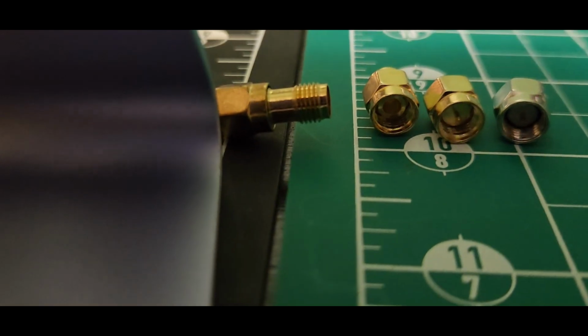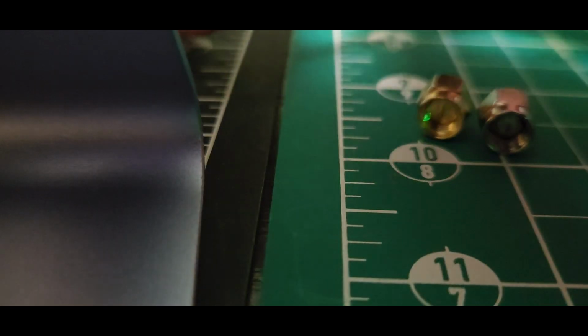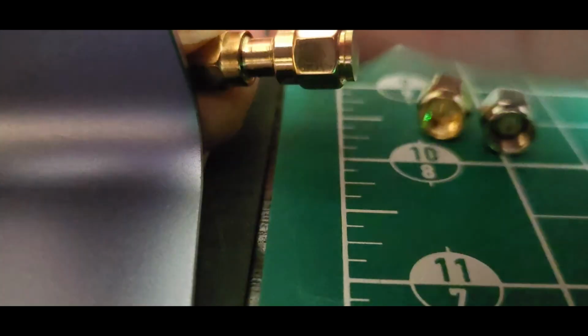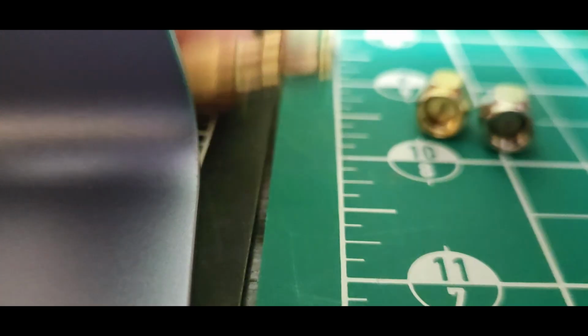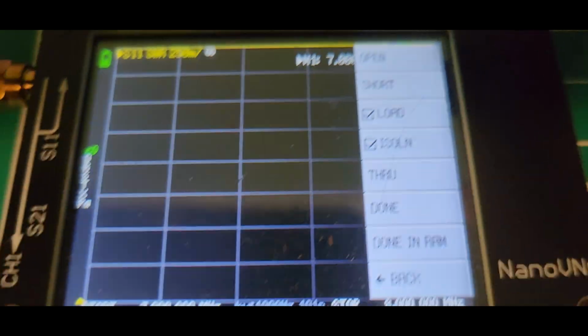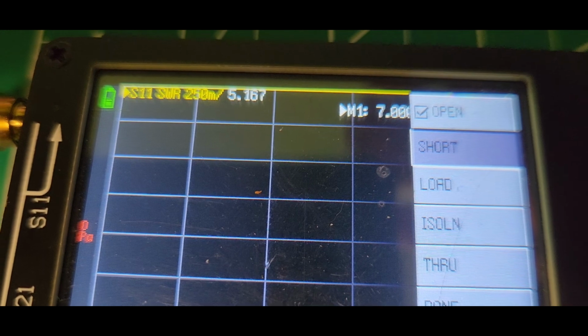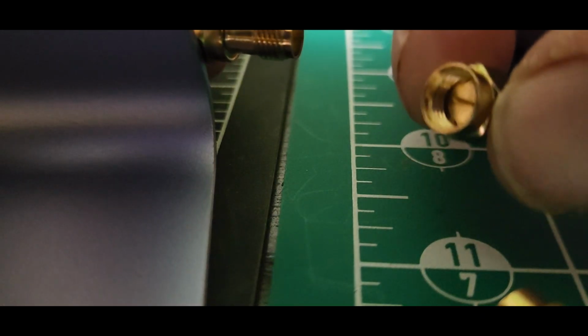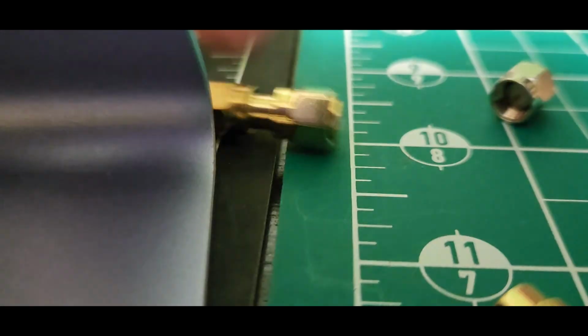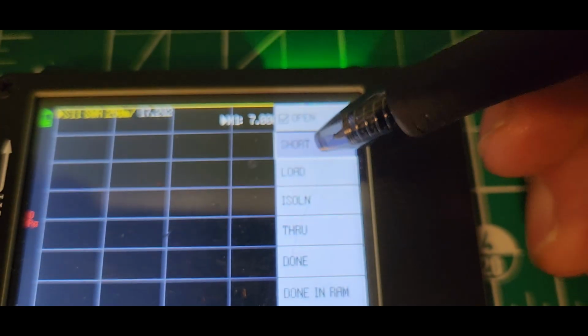So coming back to the VNA, we want to attach first our open circuit slug to the end of the cable. And having done that, we click open. And we've calibrated the open circuit condition. Next, we attach the shorted slug. Again, this one. Tighten that up, finger tight, and we run the next test. Click short.